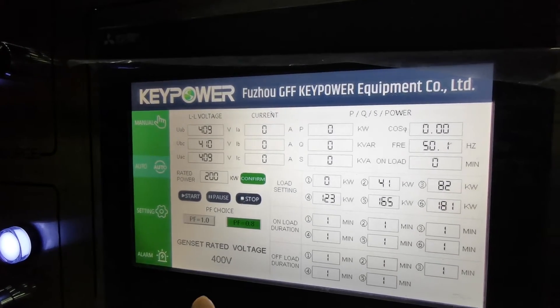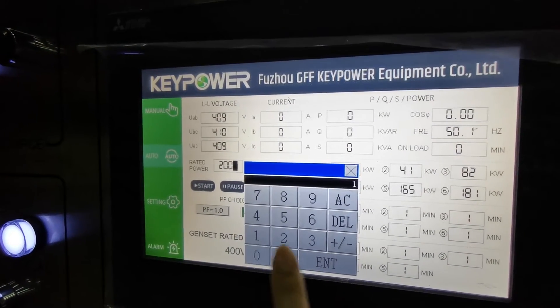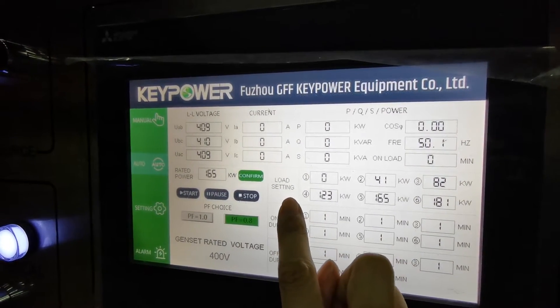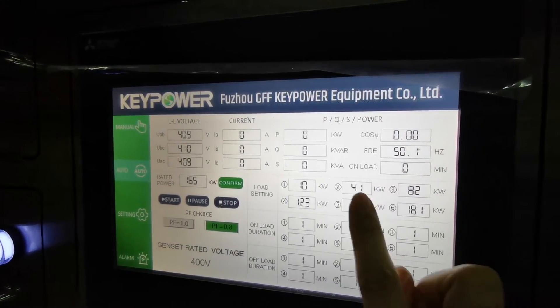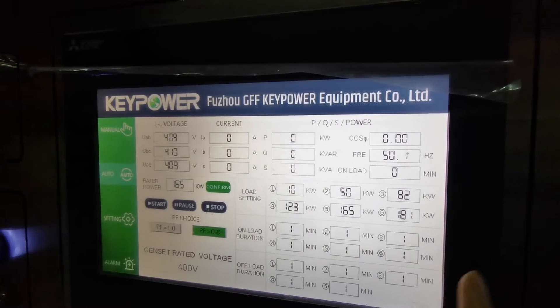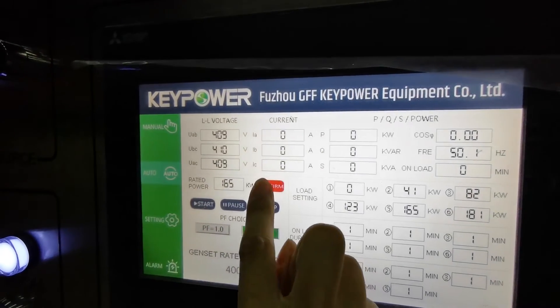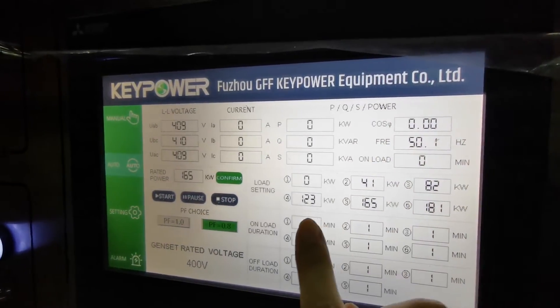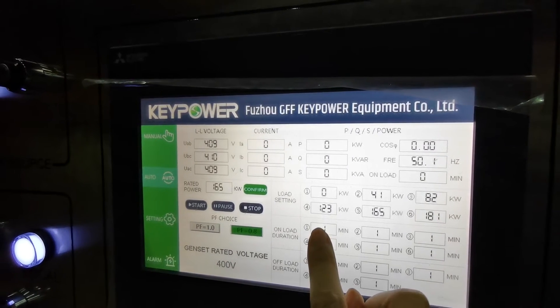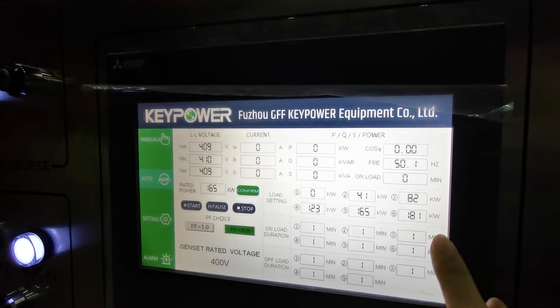The second page is auto control. For auto control, it is very easy. First, we enter the rated power — for example, 165 kilowatts. Then we can set the tested load steps, such as 10 kilowatts, 50 kilowatts, and 100 kilowatts — it depends on your requirements. Usually we choose the default setting. For the default setting, we press this button to confirm, so the power steps will be 0%, 25%, 50%, 75%, 100%, and 10% overload.